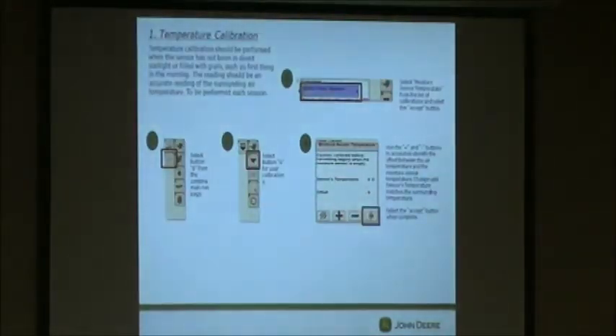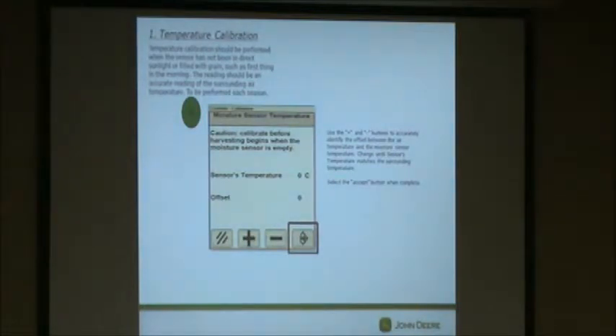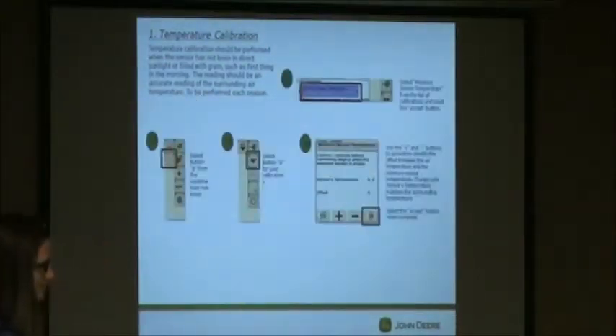You'll get to this page here, and when you get to that temperature calibration page, it's going to have a number in there, and that's going to be what your actual temperature is right now. Probably don't need to worry about an offset in it. Probably just go ahead and hit your accept button, and then it's already calibrated.